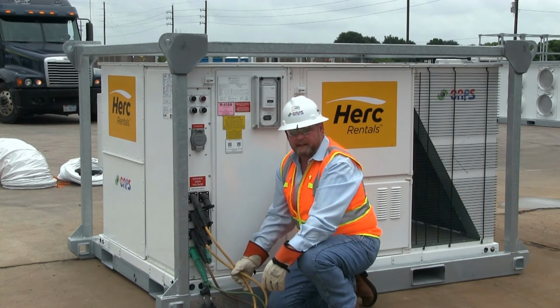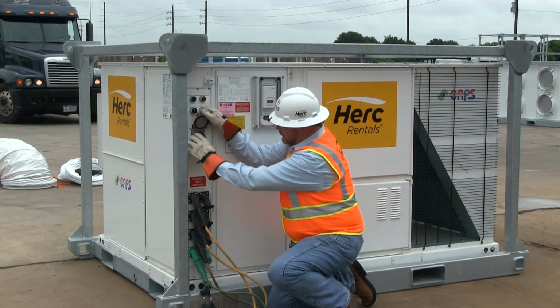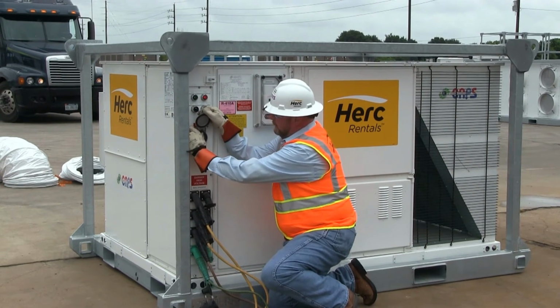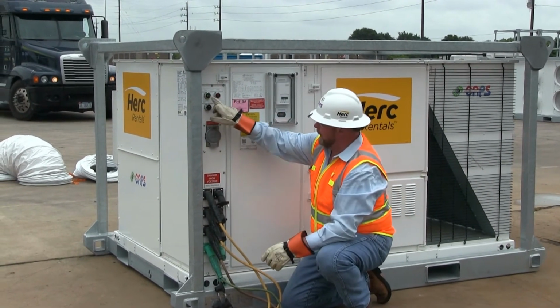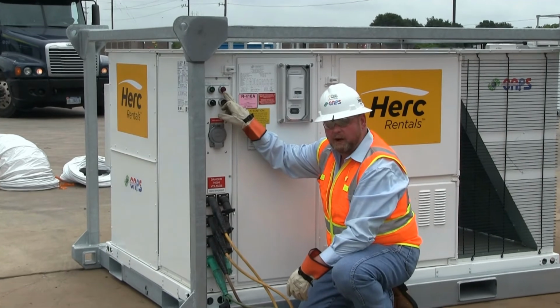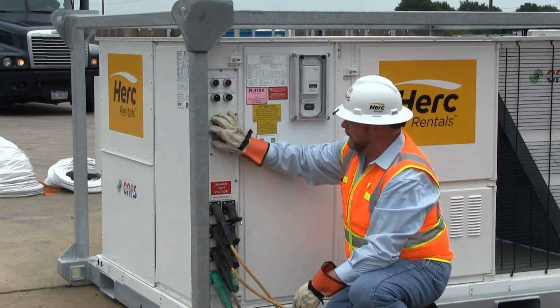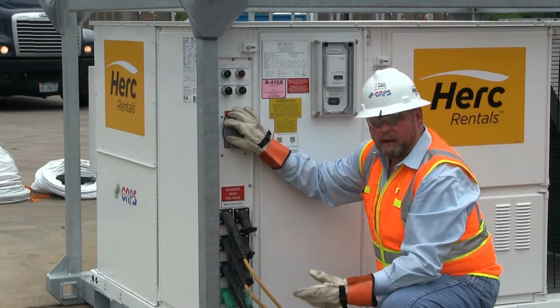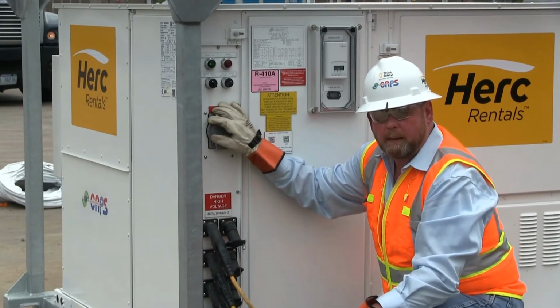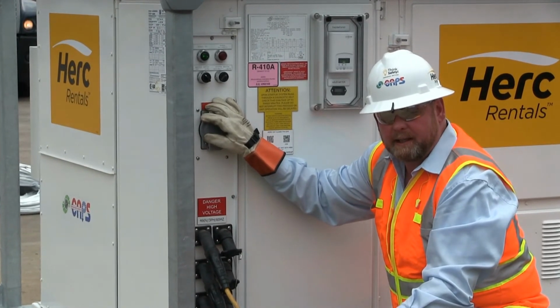We've re-energized the cable. Now we're going to close the main circuit breaker to the unit. Now we have a power light and our phase incorrect light is off. Notice as soon as we turn the power on, our blower operates. The rental equipment's indoor blower operates continuously. It does not have an automatic function.